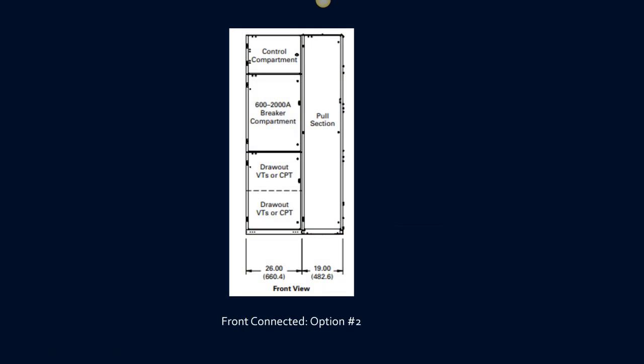This is another option we've seen some manufacturers do. Basically, you have a medium voltage cable pull section in the front of the gear. So with each section, you're not saving any width because you have to have this pull section, and they're using a narrow design in this particular option, a 26-inch wide breaker and PTs, and then they're using a 19-inch pull section, if you will, and it's a good design.